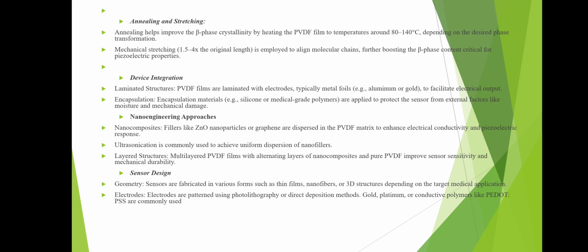So what is the phenomenon that occurs in annealing or stretching? Annealing helps improve the beta phase crystallinity by heating the PVDF film to temperatures around 80 to 140 degrees Celsius, depending on the desired phase transformation. Mechanical stretching to 1.5 to 4 times the original length is employed to align the molecular chains, which will increase the beta phase content that is critical for the piezoelectric properties. Device integration is concerned with laminated structures, where PVDF films are laminated with electrodes, typically metal foils such as aluminum or gold, which facilitates the electrical output. For encapsulation, we use silicone and medical grade polymers to protect the sensor from outside factors like moisture and mechanical damage.